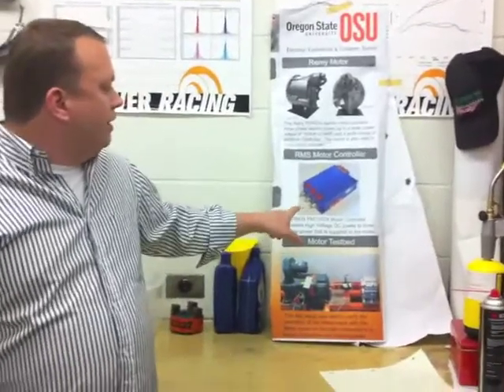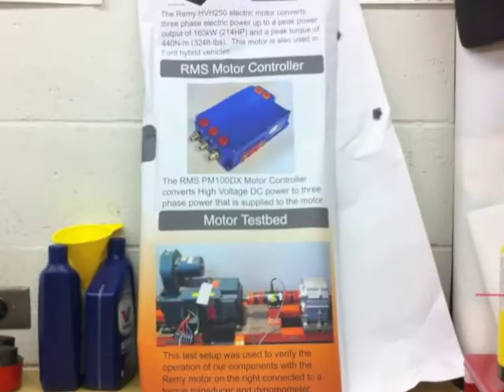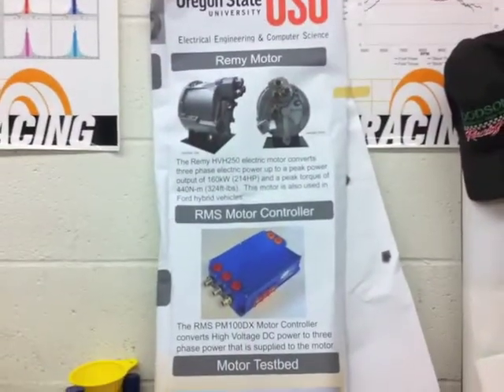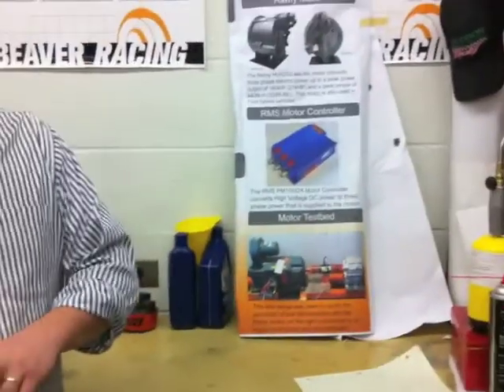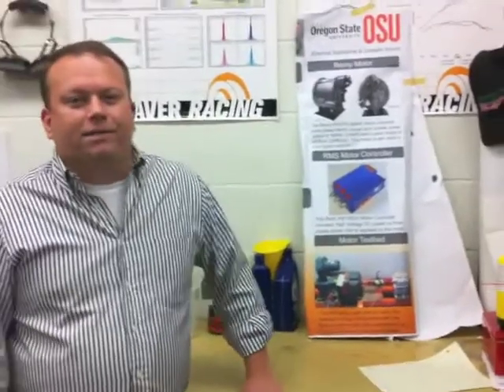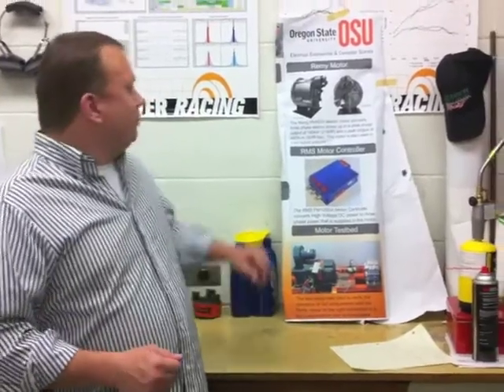There are several configuration parameters we had to consider for the motor controller, including mechanical and electrical phase matching, to make sure the resolver, which shows motor position, agrees with where the motor actually is and can communicate that information from the motor to the motor controller.